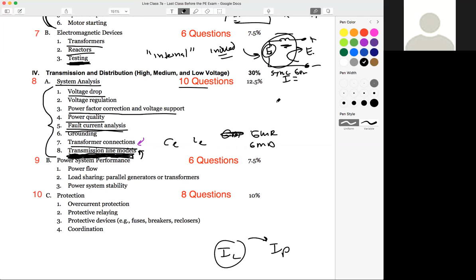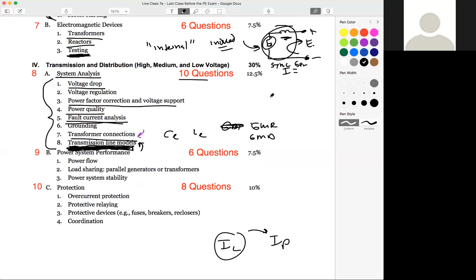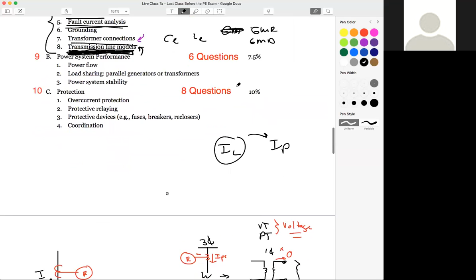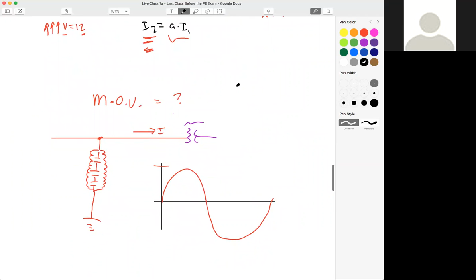Keena said, the power factor is 0.85. Shall we use the Z value from table 9 without the angle value? However, if we take R and the X value, the angle should count. Okay, let's pause here and talk about that for a second, because I see Shamil is talking about that too.